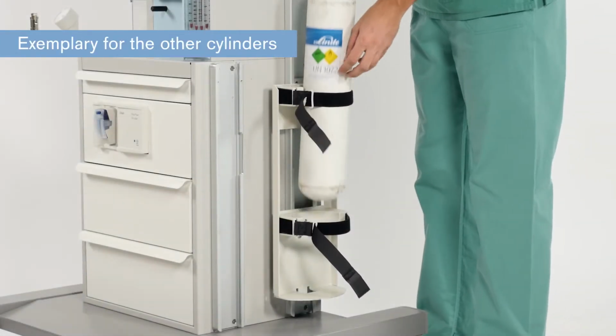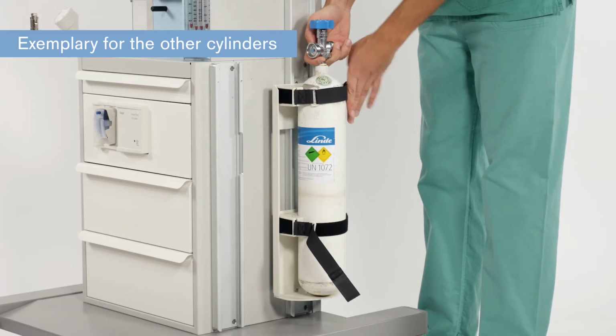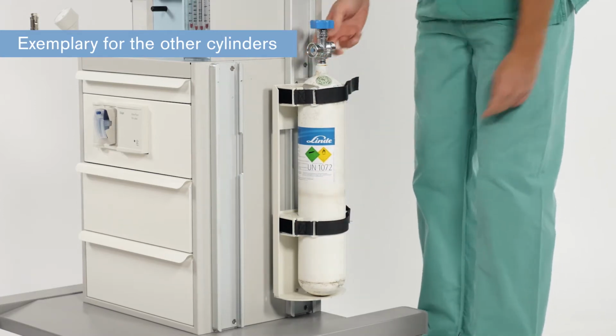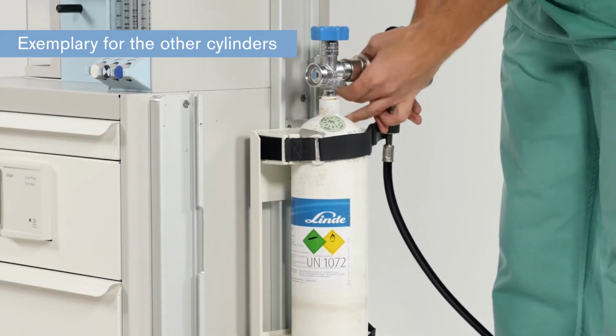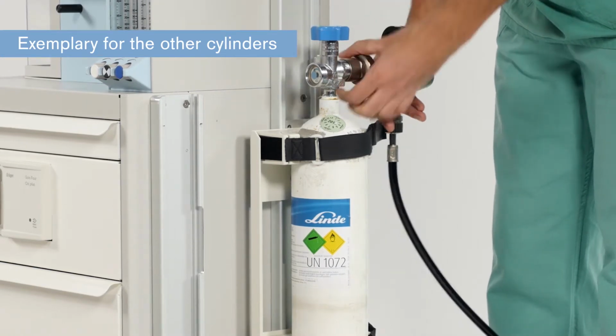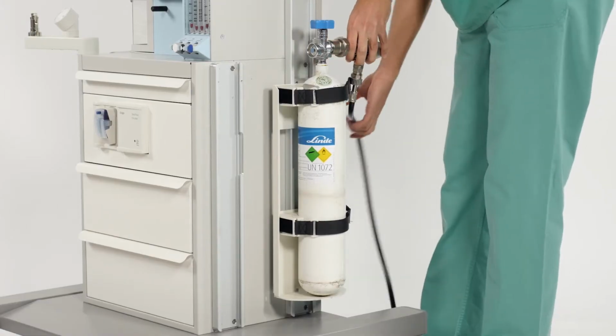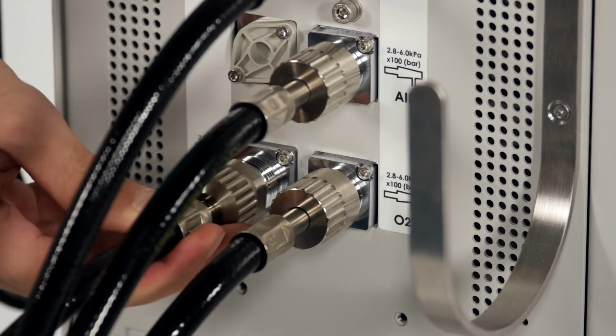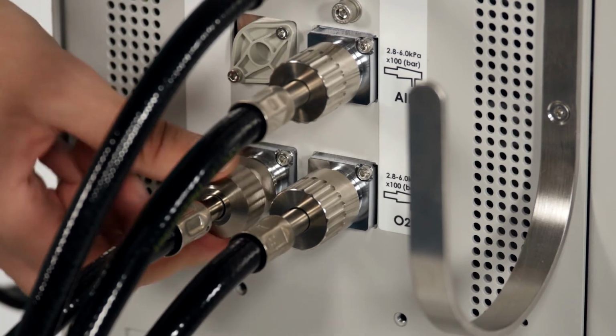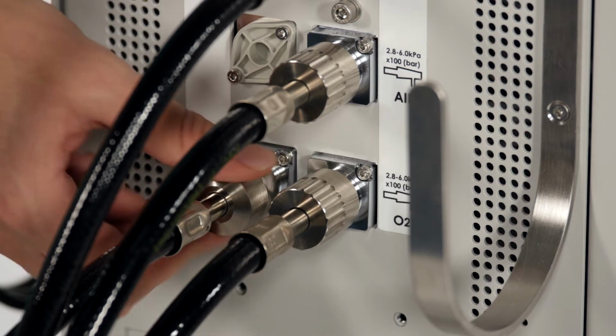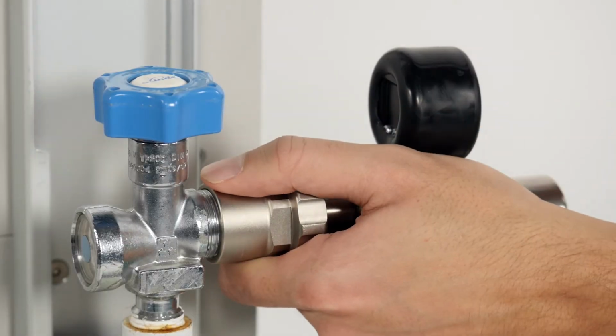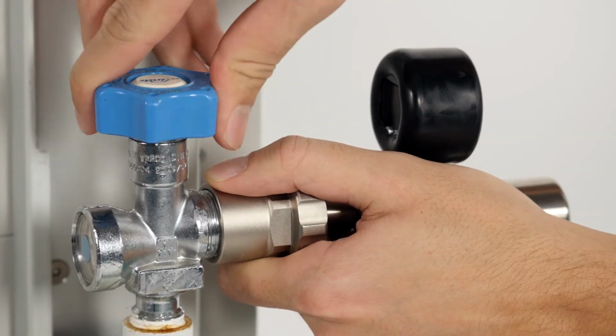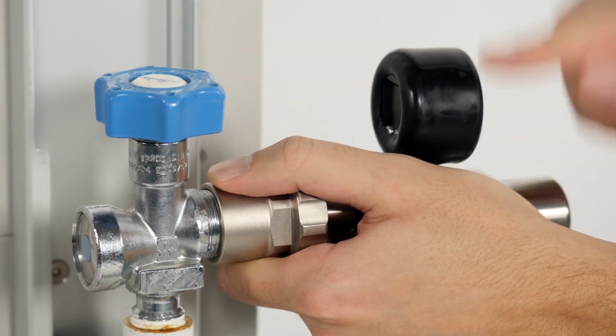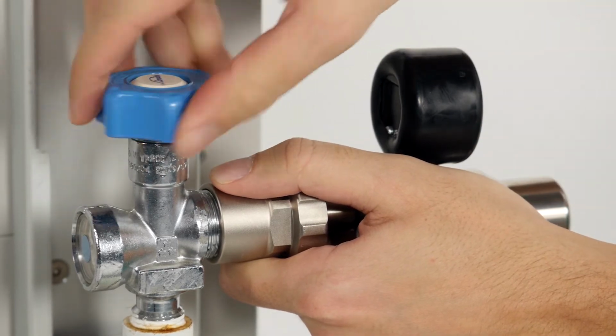Place the full cylinder in the cylinder holder and secure it in position. Screw the pressure regulator onto the cylinder valve. Screw the compressed gas hose to the pressure regulator and to the connection of the gas inlet block. Open the cylinder valve and check the pressure on the pressure reducer. Close the cylinder valve.